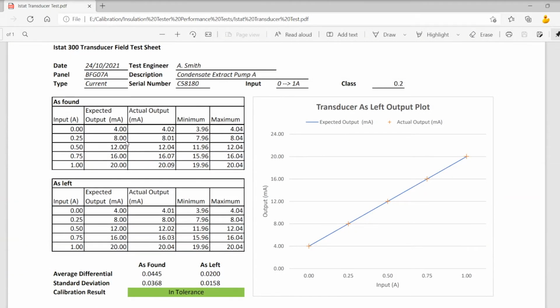So this shows what I've actually done: the date, where the transducer came from, the panel it was from, serial number, the type, and its rating. That's its class, it's 0.2% class, and this is where I get the minimum and maximum values from. So for a transducer, the class is 0.2% of the maximum output, which is 20 milliamps. So I have a 40 microamp tolerance on any of the readings that I take.